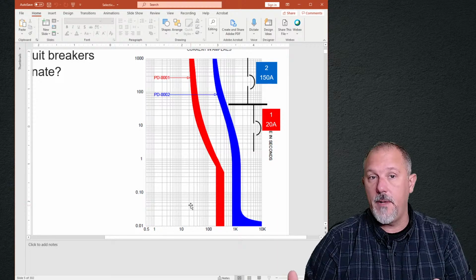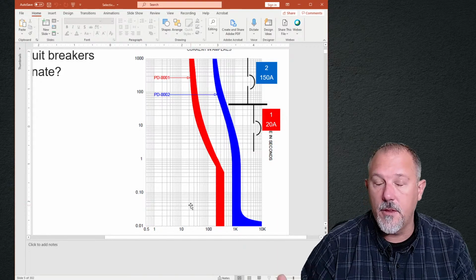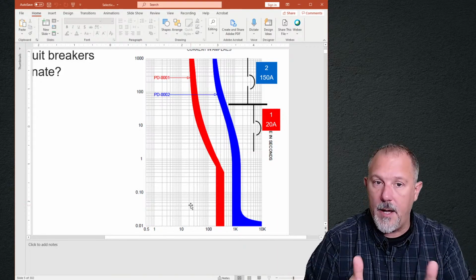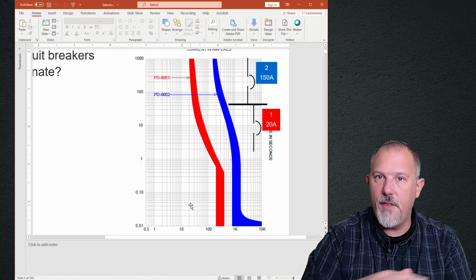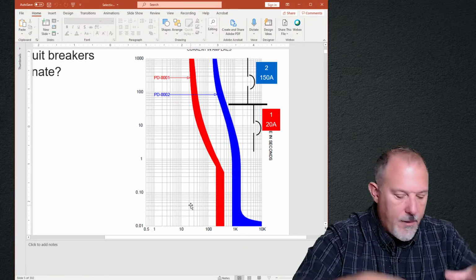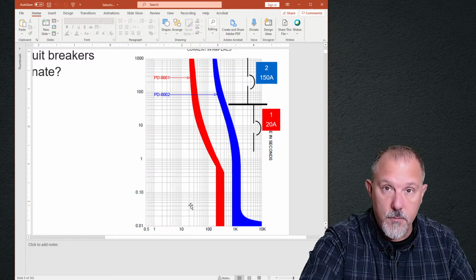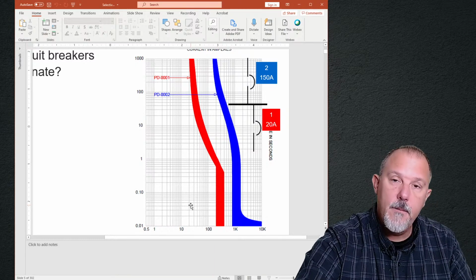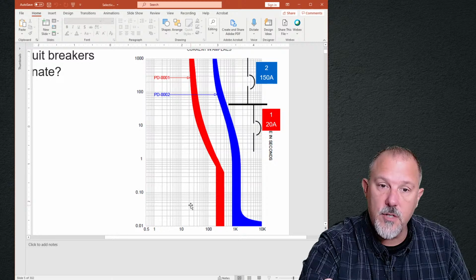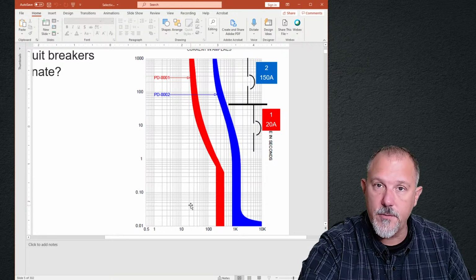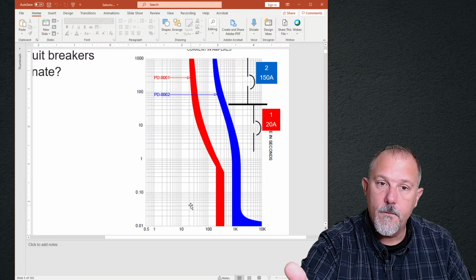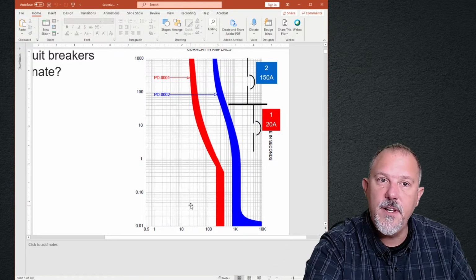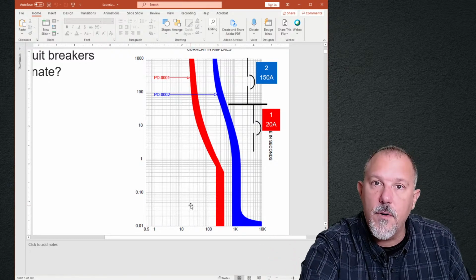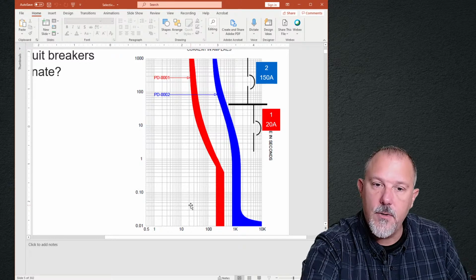Now, we can have an argument and a debate on whether or not it should be the three-phase bolted fault current value, but regardless of that argument, if I look at the National Electrical Code, that argument's a moot point, because it's very clear that I have to make sure that these work all the way up to the three-phase bolted fault current value. But even if I say, well, talk about ground fault current, I still have the same issue.